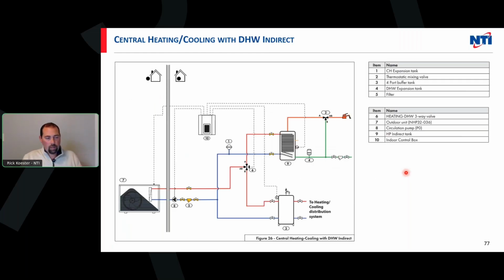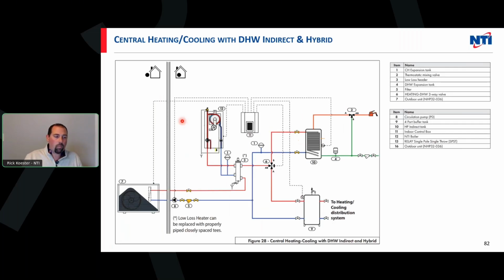Same thing, I didn't put all the pages here for time's sake, but for central heating and cooling now with the addition of an indirect tank, now we need a diverter valve. Again, you're going to see the minimum that we need as far as sensors. We do have other features they may want to take advantage of, in addition to this, but this is the minimum they need to get a system operating properly.